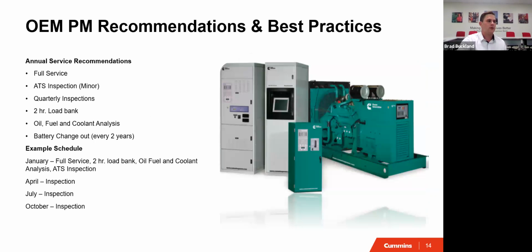So to alleviate the most inconvenient parts, we offer a package—the standard one we recommend as a manufacturer. It includes the annual full service we talked about, an ATS inspection (a visual inspection), quarterly maintenance visual checks, a 2-hour load bank test, oil, fuel, and coolant analysis, and a battery change-out every 2 or 3 years. We like to get it within 2 years, though people stretch it out—batteries don't always die at 3 years, but often they do, so we recommend between 2 and 3.